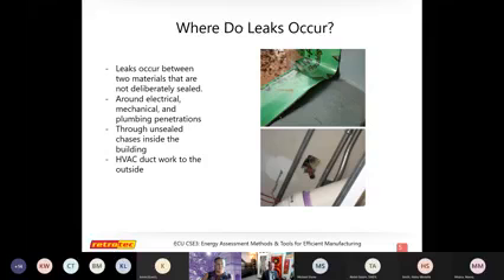And then any holes that we have going through what would be our air barrier, whether it's plumbing, mechanical, or electrical. If you can see here in this photo, this is a massive hole here that was cut through these pipes and then not sealed back over. Really, if you're going to run pipe, you should use a hole saw and then seal around it. You don't have to cut out a great big rectangle like this to run a small circular pipe. But we see a lot of this stuff in all types of commercial buildings.